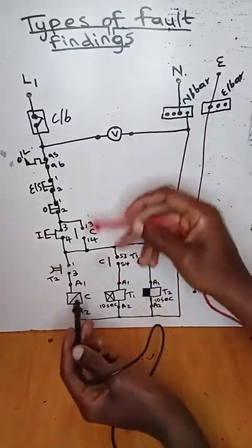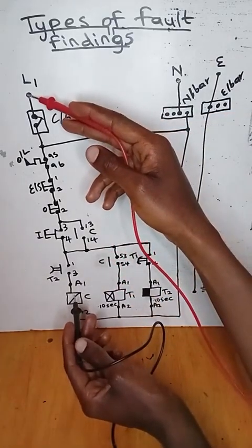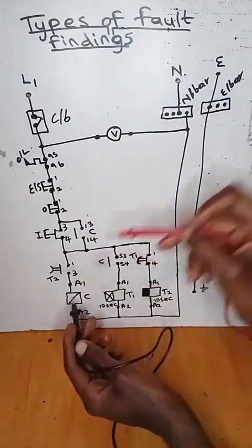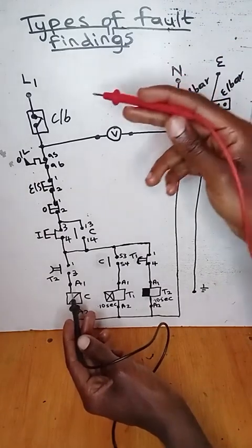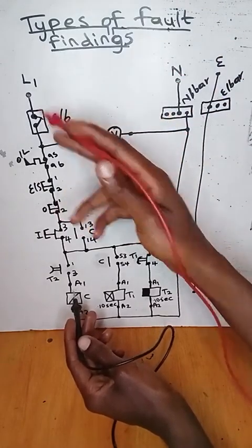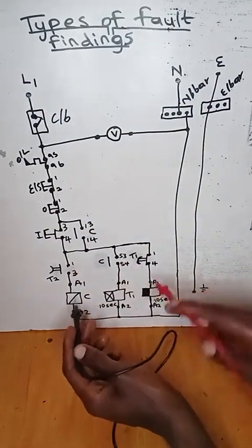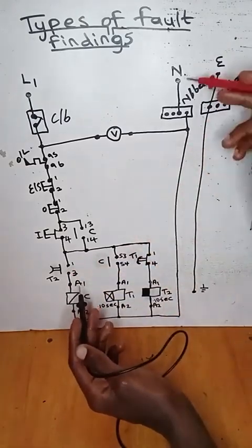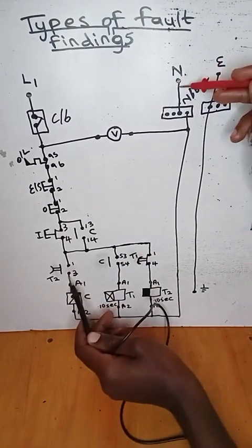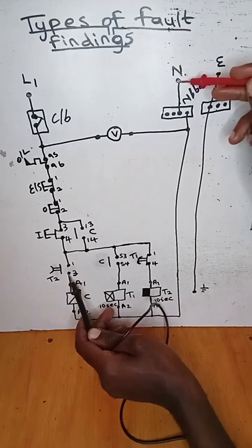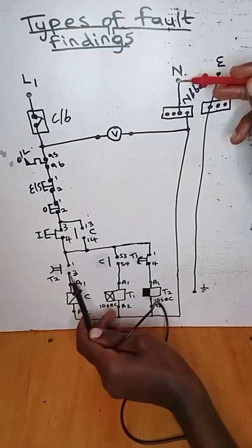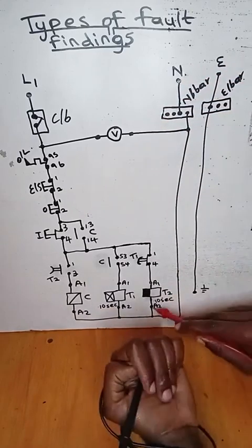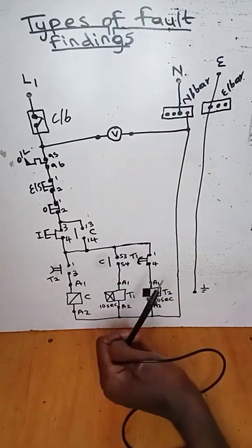So to check our live current from where it starts until this A2, since we have tested live from where it starts until here, here, and here, and from this contact, if we cannot press anything, we'll put neutral, and we'll put live after the normally open contact of the delay timer, right? From here, which means we have tested live from here to here, with the neutral from here, here, and all the A2s of the coils.